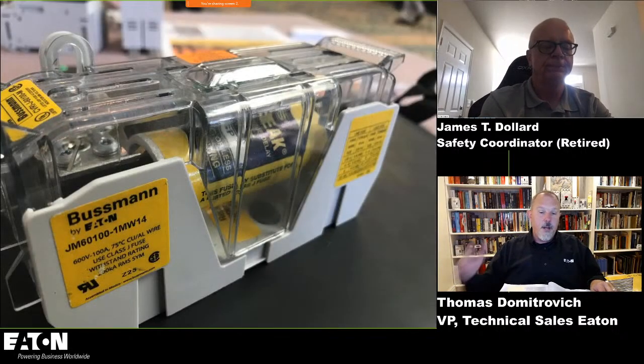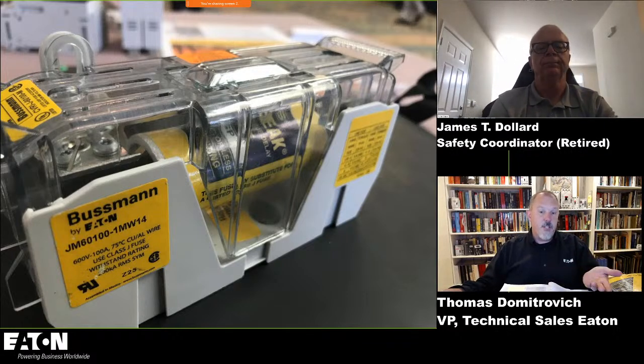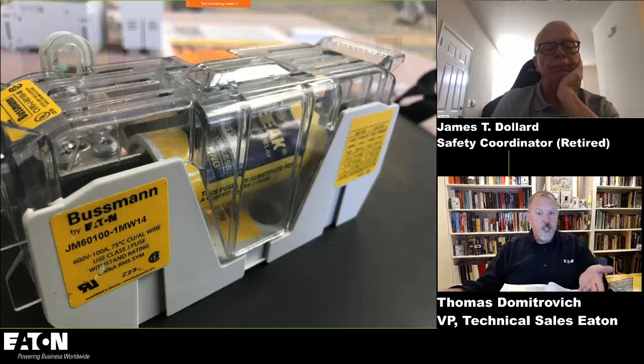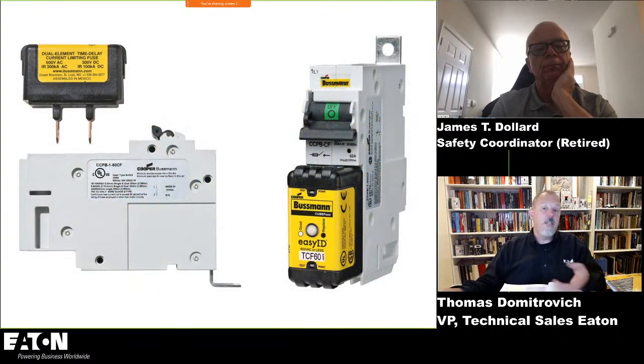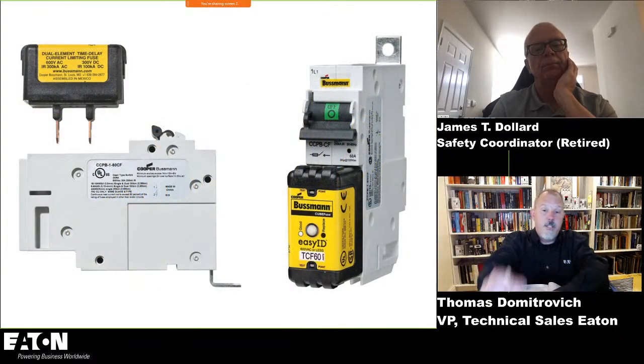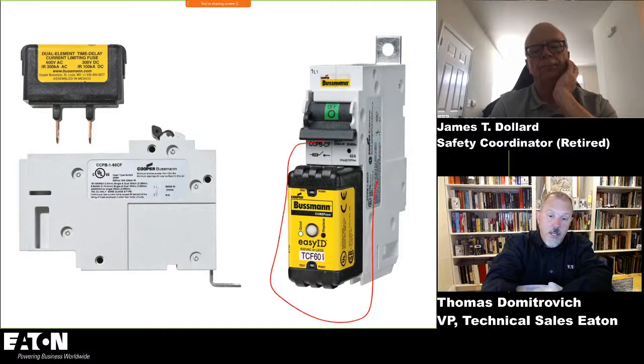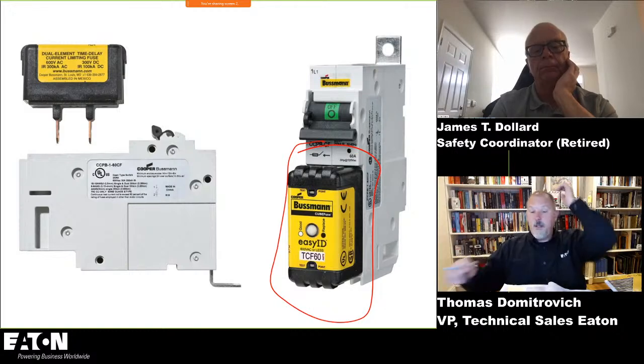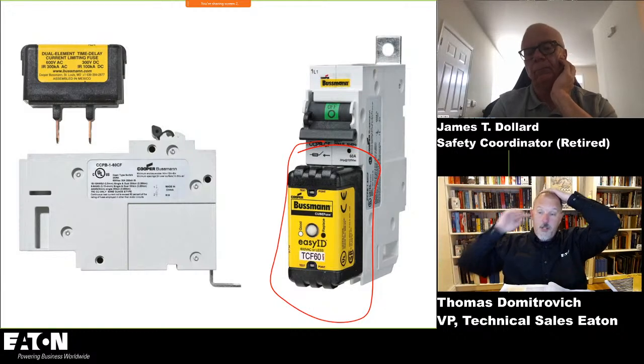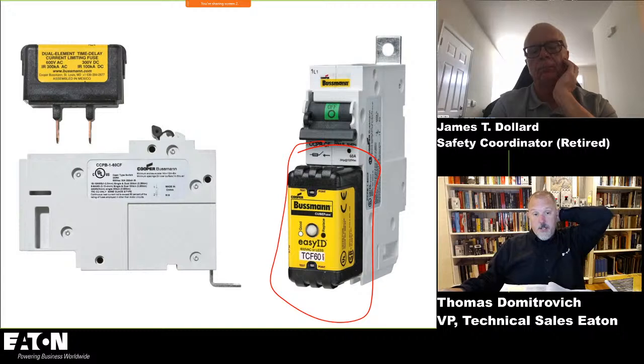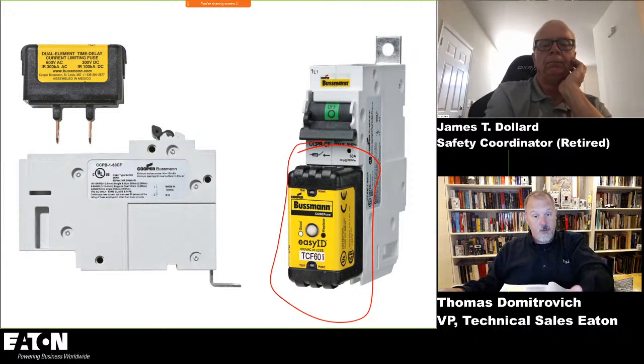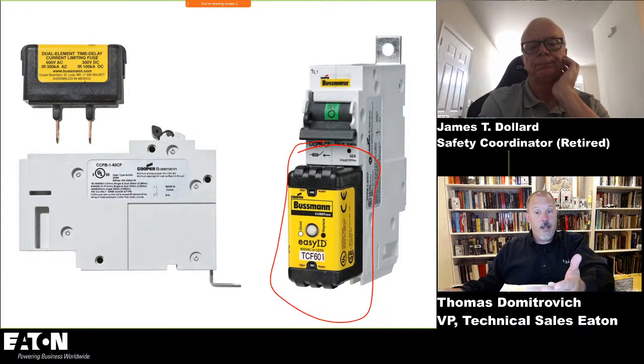And then other barriers might be solutions like finger-safe products that you install in industrial control panels. You install products like these through the dead front, so you can change the fuse out and not be exposed to energized parts. So there are solutions on the market that people can specify that aren't required by the code, but add an additional level of protection.